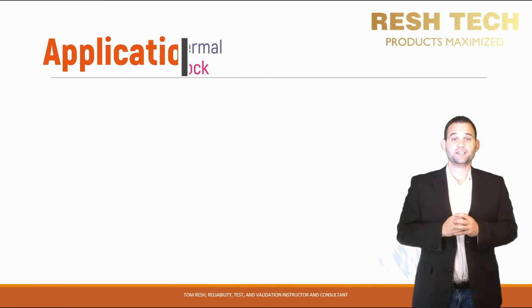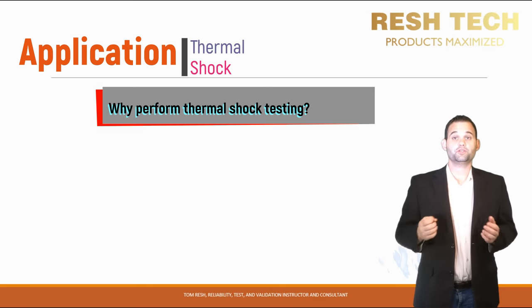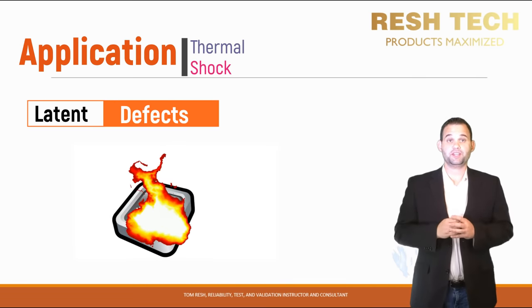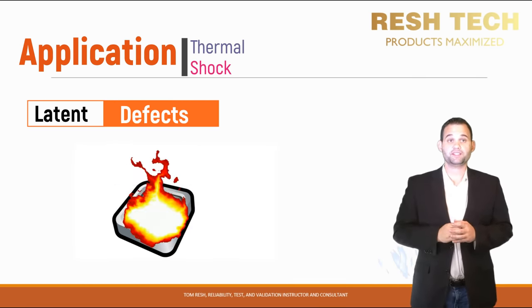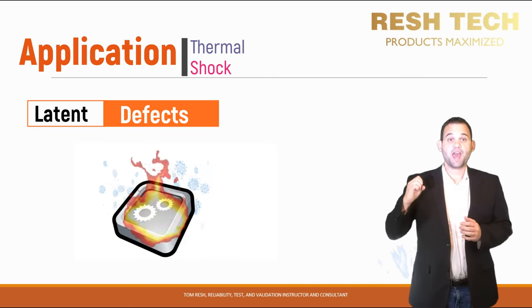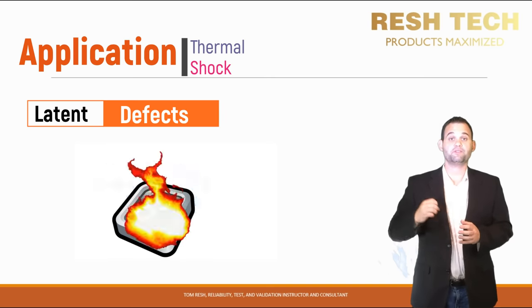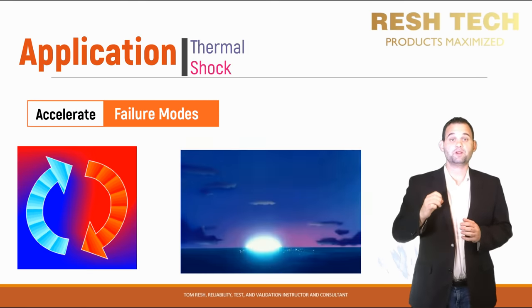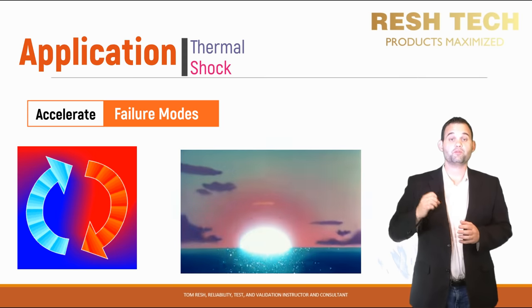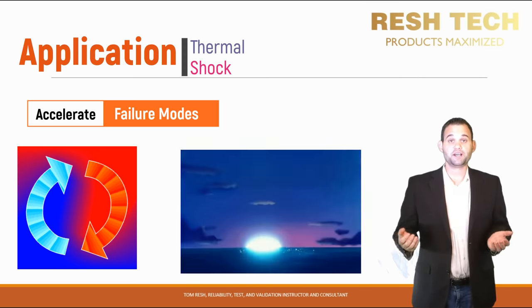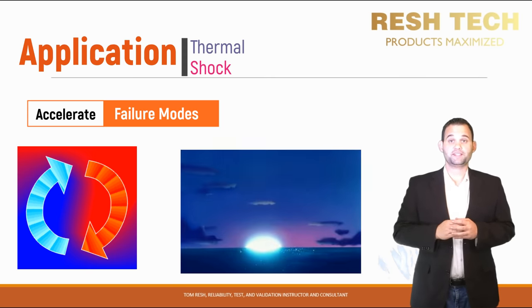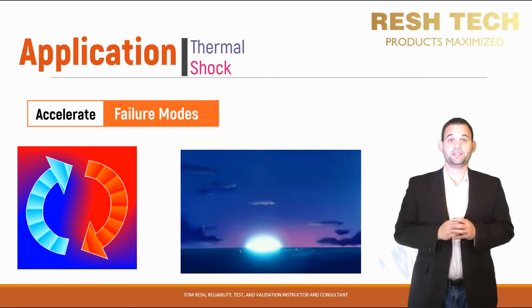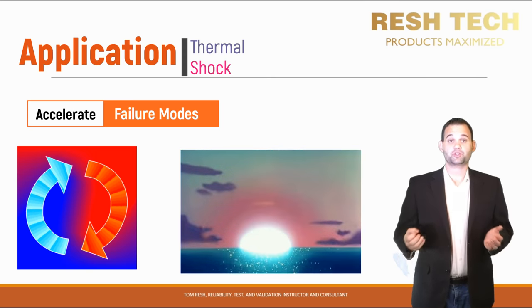Let's quickly discuss the intent of thermal shock testing. Thermal shock testing is typically used for one of the following reasons. The first is to detect latent defects by rapidly changing the ambient temperature of the part or system, which can help you find weaknesses in your design and production process as a result of rapid contraction and expansion of materials. The second reason is to accelerate the effects of environmental temperature changes — especially with systems placed outside and exposed to the elements — and quickly assess resistance to cyclical temperature stresses that produce mechanical or material fatigue.